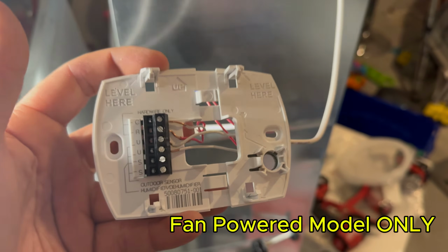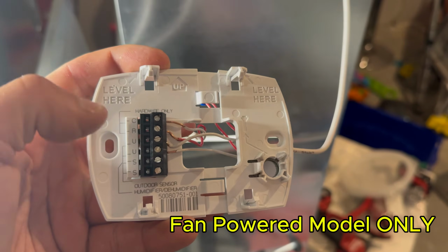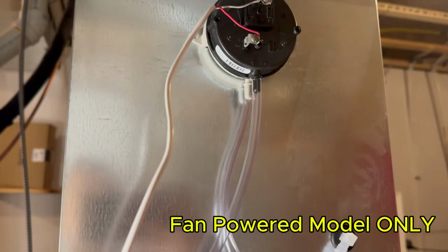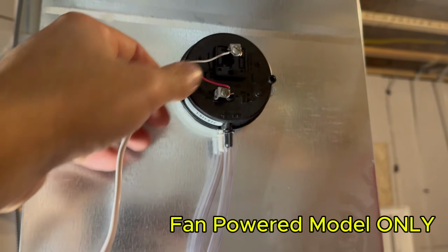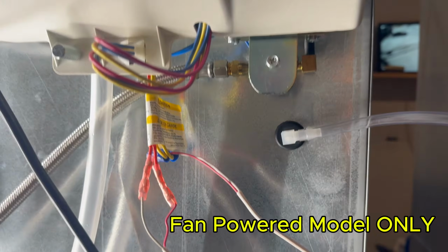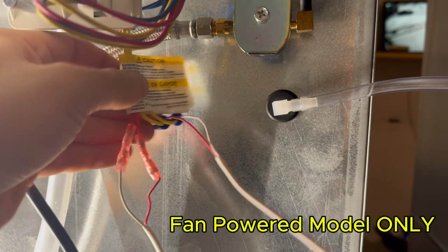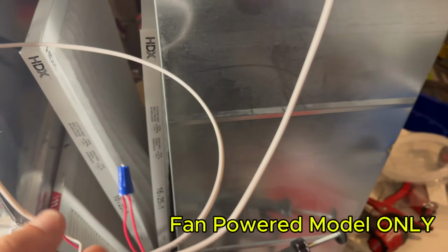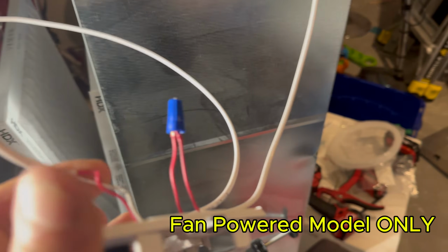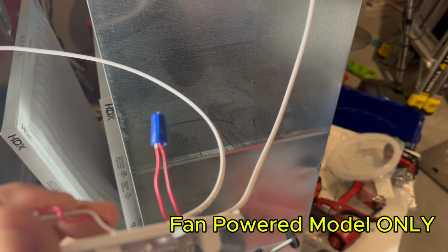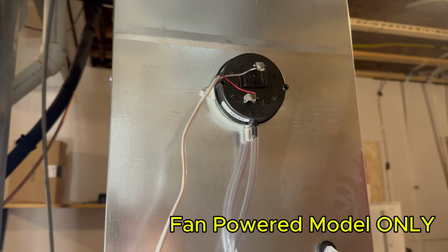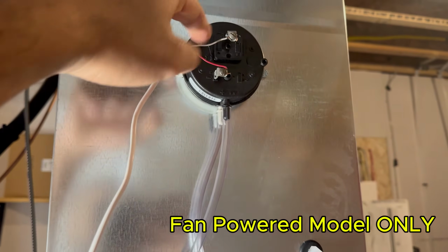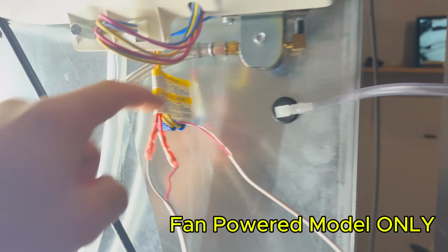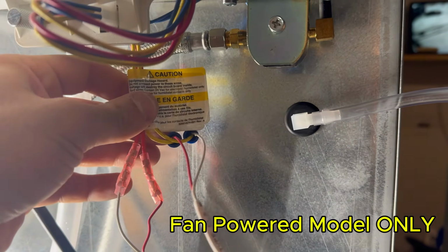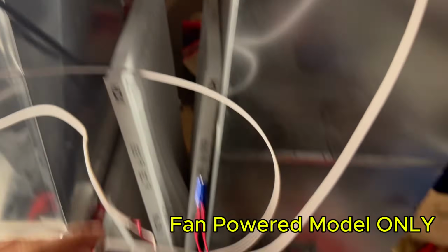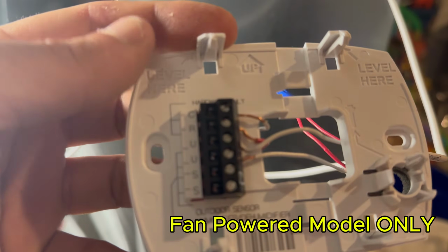This is what's going to power your digital humidistat, C and R. Now you're going to take the red wire coming from the pressure switch and the red wire coming from the yellow terminal on the humidifier, and you're going to connect those 2 together. Just the 2 red strands, as I've done here with a wire nut.